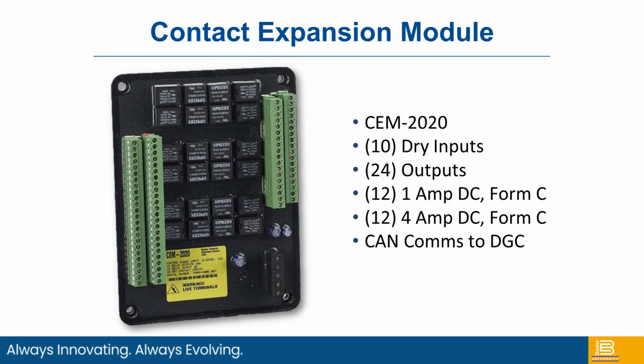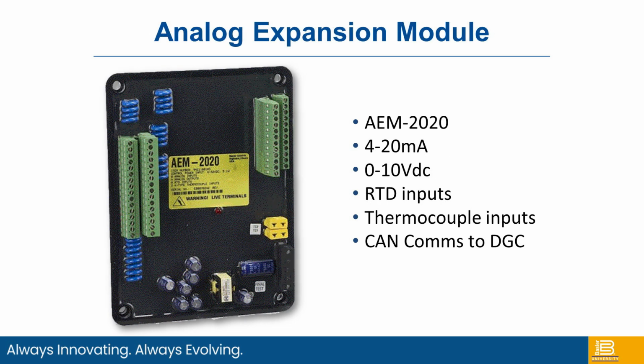The contact expansion module has 10 dry inputs and 24 outputs, 1 amp DC form Cs and 4 amp DC form Cs, and this utilizes CAN communications to the DGC. You'll also see the analog expansion module is very similar: 4 to 20 milliamp, 0 to 10 volts, or RTD, thermocouples, all that's configurable through the BESTCOMS software. Quick little diagram of the RS-485 communications to the different accessory modules.